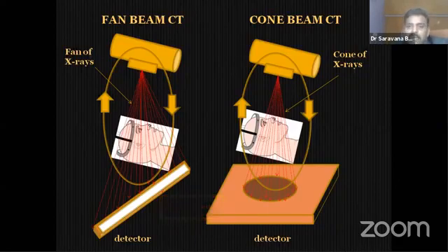Okay. The cone beam CT is going to rotate around the patient head. It's going to deliver multiple 2D exposures only. It's not going to deliver a 3-dimensional radiographic exposure. It is going to deliver multiple 2D exposures only, around 600 to 800 exposures in one single rotation. All the information will be received by the flat panel detector or scintillator detector. The information will be sent to the computer. We'll be seeing a lot of images that are called the basis images. All the images will look like a cephalometric image. That is called the basis images. These basis images, this data, is called raw data.